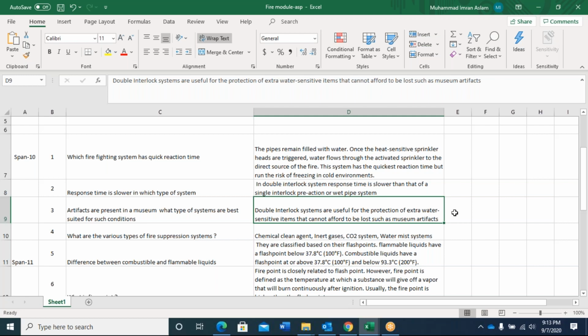These are usually deluge systems. In the deluge systems, wherever there is a sensitive area, like a cold store where there are chances of freezing, what we usually do is the pipe is filled with air. So in a single interlock, the detection system gets activated. When the detection system gets activated, the air is released immediately from the pipeline. When the air is released, the water reaches up to the sprinkler head. We have a fuse bulb there, so whenever the temperature is reached, it melts away and the water sprays in the particular area.